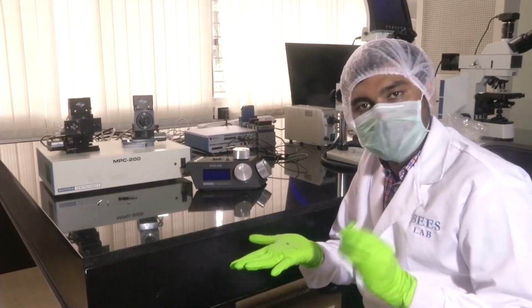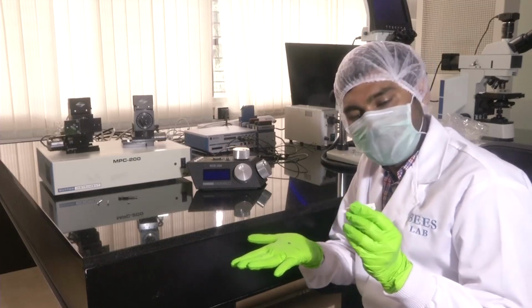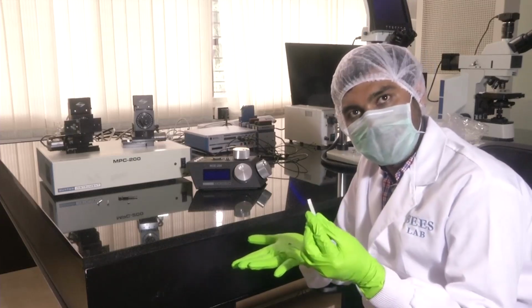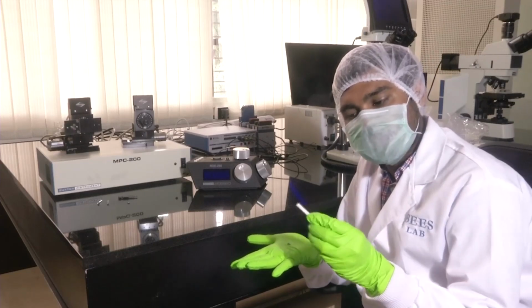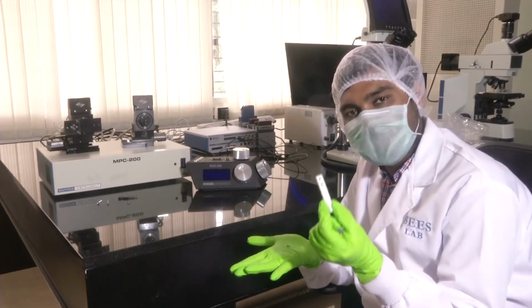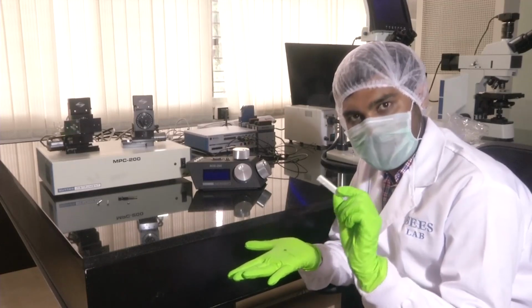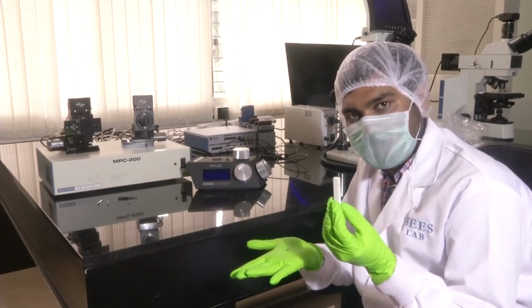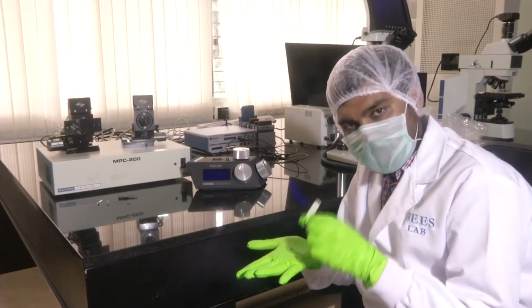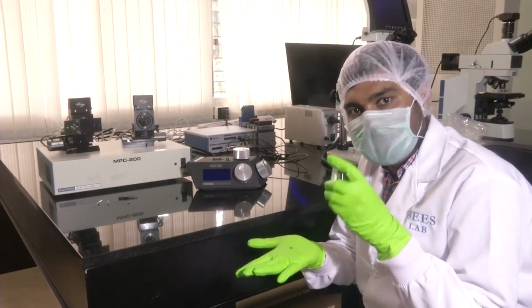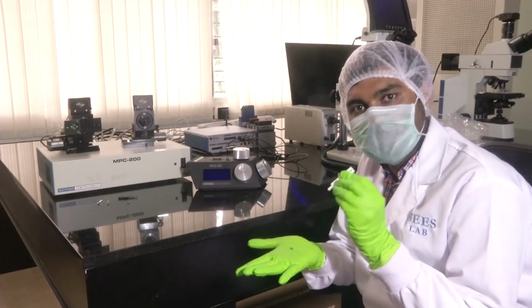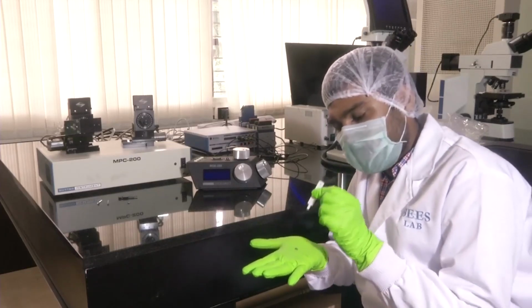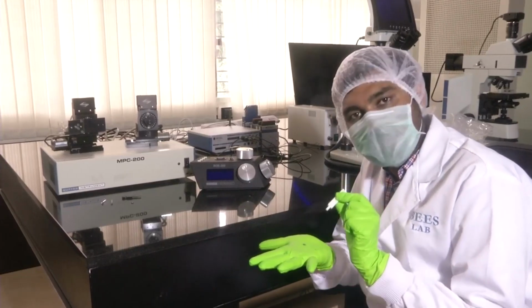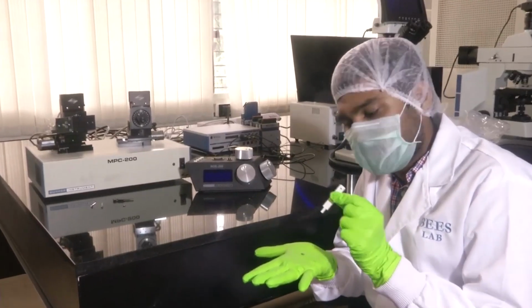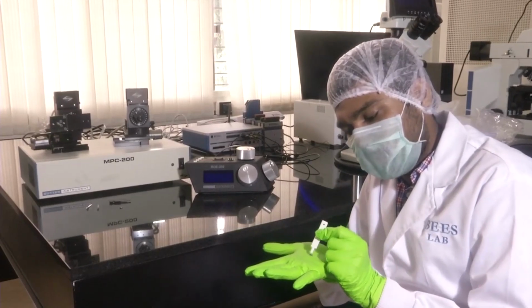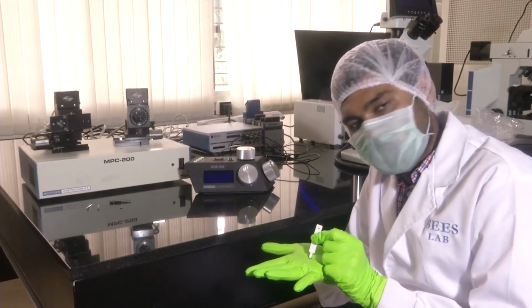Now, we want to measure the stiffness of the tissue. For that, let us say this is something called an indenter. This is a 3D printed indenter. This is macro scale, not micro level, but it is for understanding purposes. What does an indenter do? It indents or pokes or manipulates the surface of the sample. So, let us say we have brought this indenter, and for the time being, for characterizing the sensor, we are pressing the tissue with the indenter.